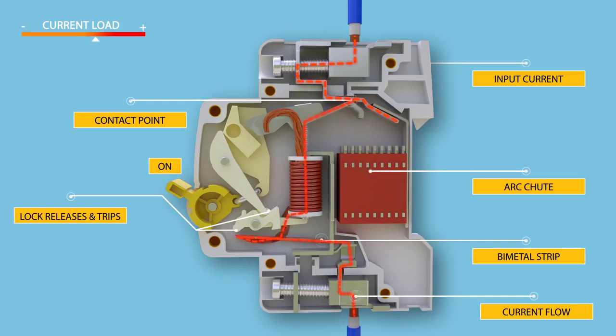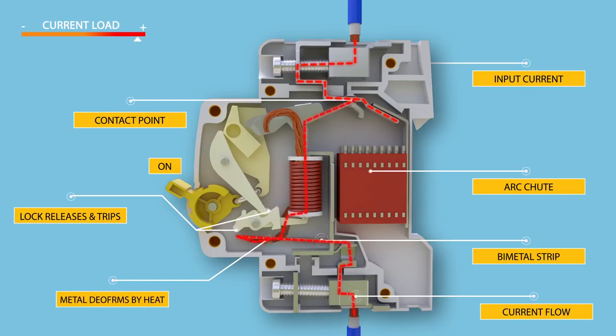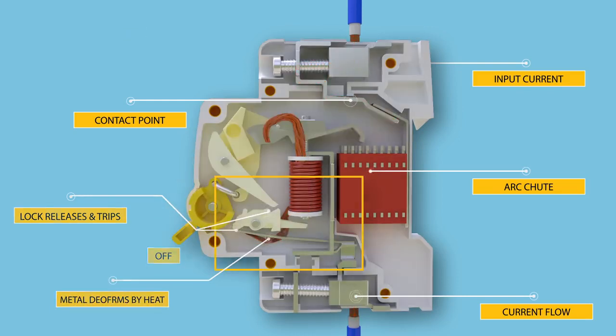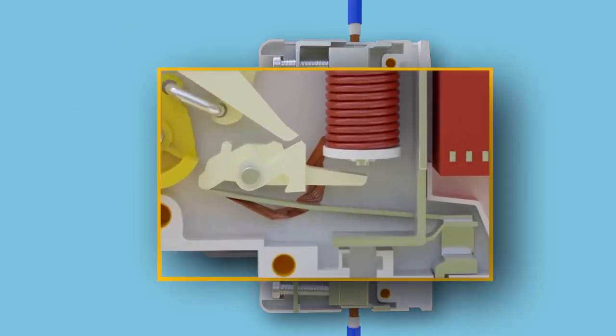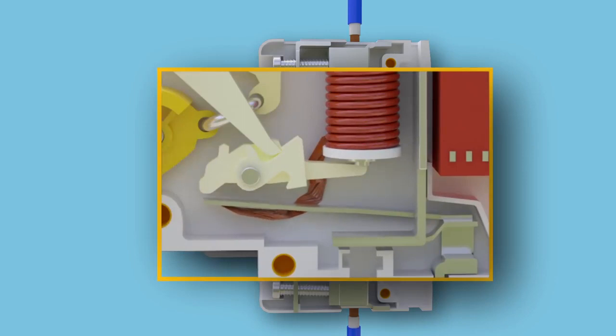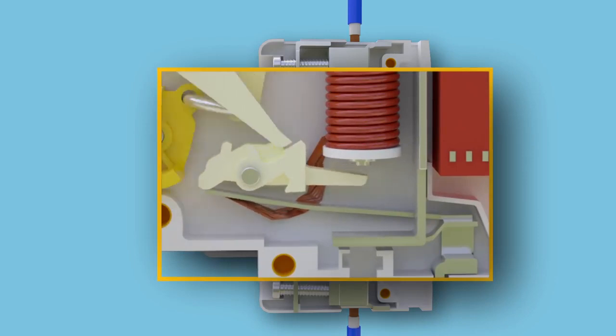In tripping operations, an arc is formed when the contacts start separating. This arc is then forced into the arc chute plates, where it is formed into a series of arcs, and at the same time energy is extracted and the arc cools. A closer look at how the tripping mechanism works is shown in the animation.